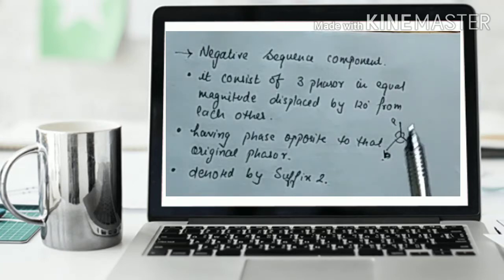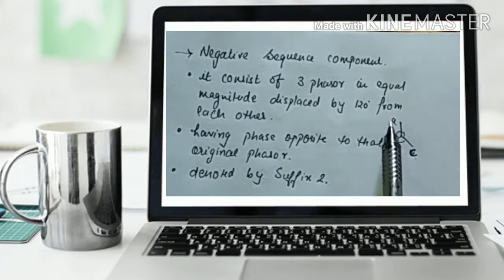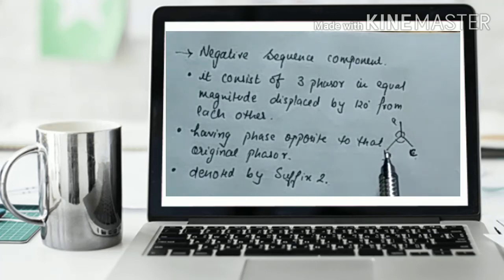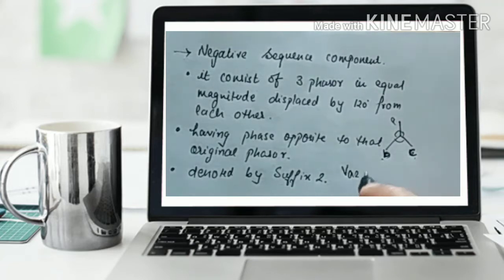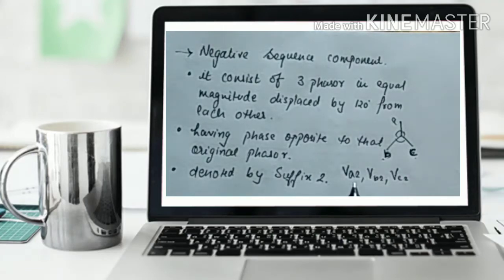Negative sequence component consists of three phasors of equal magnitude with a phase displacement of 120 degrees, but having opposite phase sequence — instead of ABC we have ACB. It is denoted by suffix 2, meaning Va2, Vb2 and Vc2. For positive sequence we write Va1, Vb1 and Vc1, while for negative sequence we write Va2, Vb2 and Vc2.